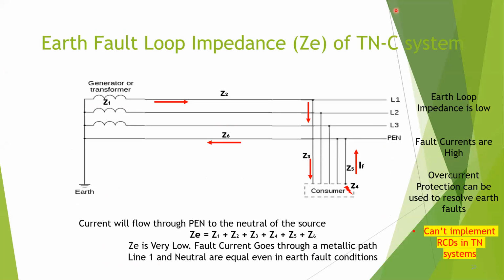And this is the earth loop impedance path of the TNC system. Let's say our fault is in L1, similar to the TT system we considered earlier. Your fault current is coming, and from the inside it is shorting to the enclosure, and through the enclosure it is going to neutral again. You may remember earlier I said this wire you do not need, you can just put a wire here and connect it to here without an issue, because it is the same potential. And mostly from the inside this wire is connected to a neutral point at your circuit. So that is how an appliance for a TN system is used.